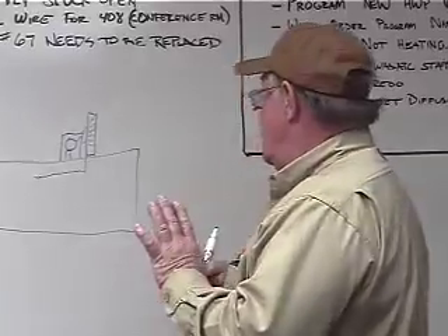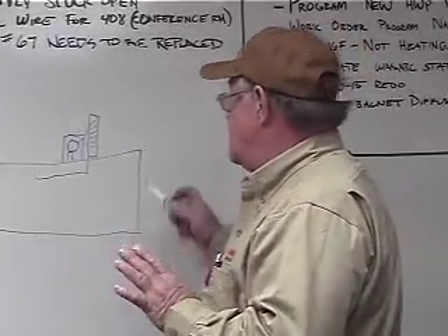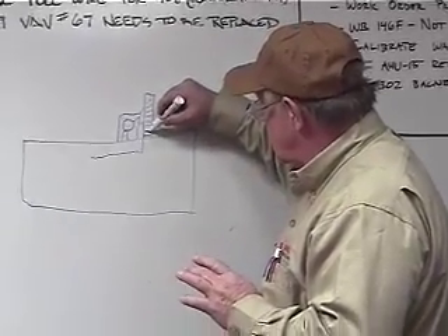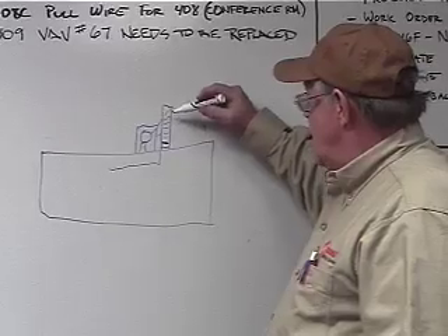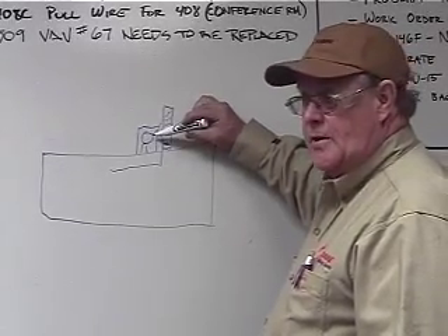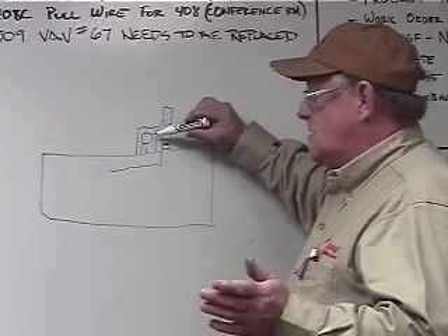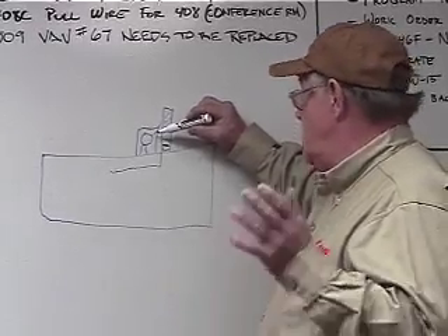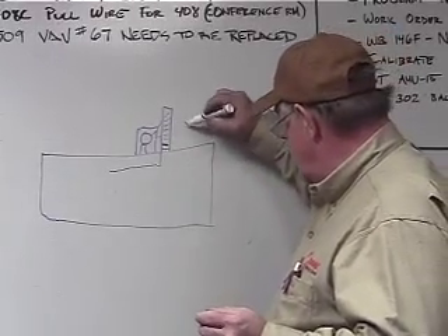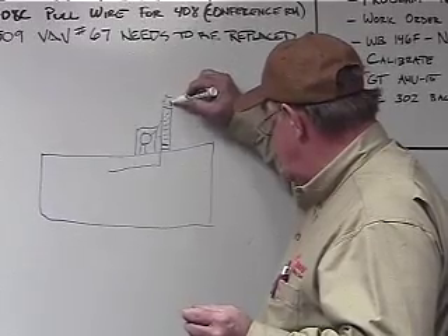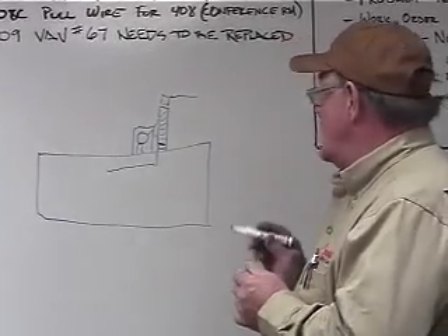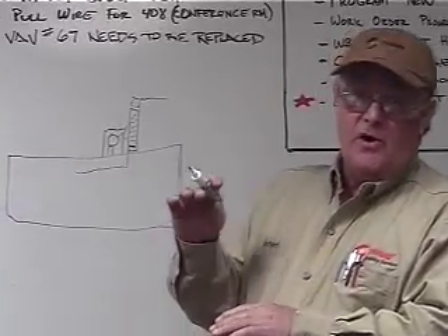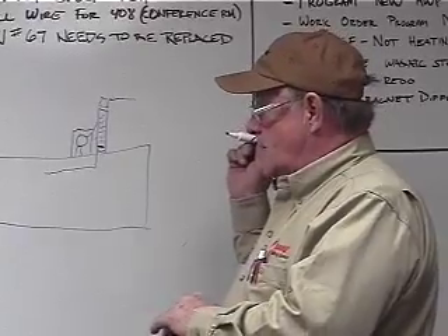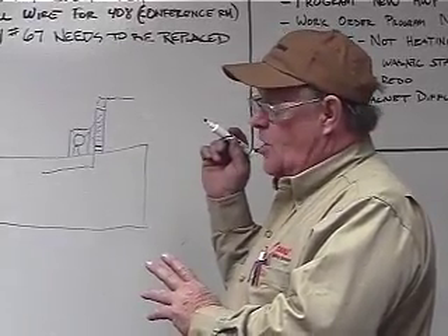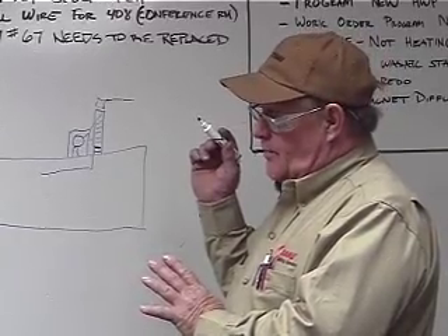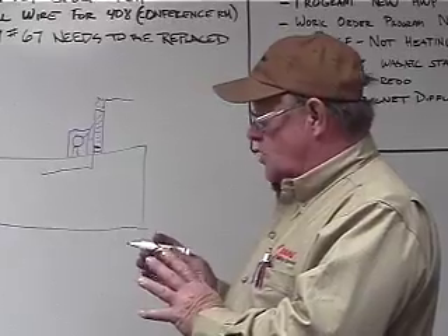Now, if for some reason you've got air in there, it's not going to condense and your refrigerant level is going to stay low. In that case, what happens is the suction line on this little compressor over here starts to drop in temperature. Once it gets down to about 18 degrees Fahrenheit, it turns on what we call a purge pump up here on the top, which goes out to a vent line. At 18 degrees, it's going to remove all those non-condensables and send them out into another tube that we call a charcoal filter. So these non-condensables will go into this charcoal filter.